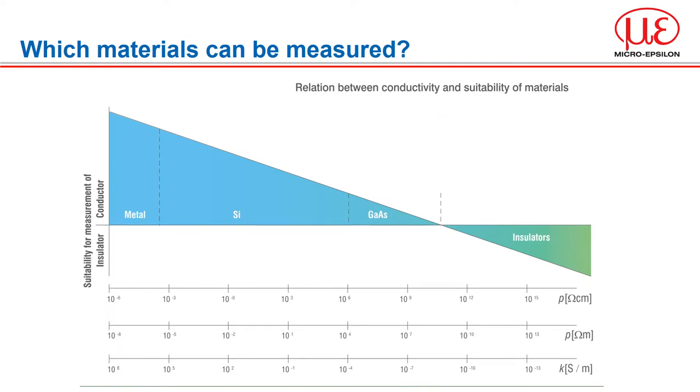In between metals and insulators there is a large range of semiconductors. Most semiconductors can be measured very well as electrical conductors. The requirement is that the capacitive part of the total impedance is still significantly larger — greater than ten times that of the ohmic part. This is almost always the case for silicon wafers irrespective of the doping. Nevertheless, semiconductors with poor conductivity, for example gallium arsenide, can also be measured as conductors under certain circumstances, and you should talk to us if you have this requirement.